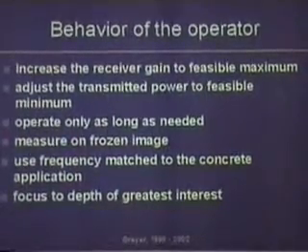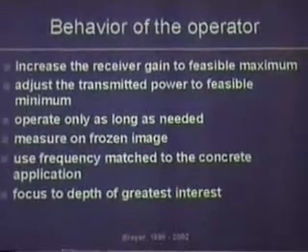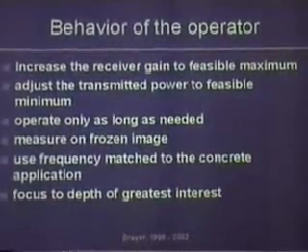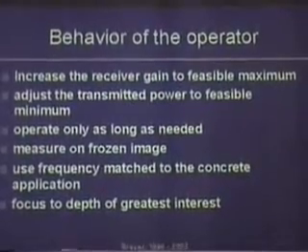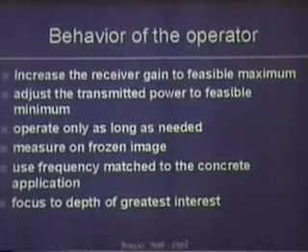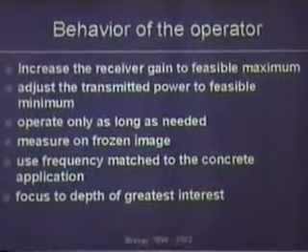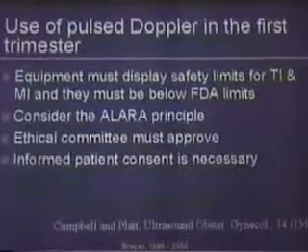Frequency and focal zone, everything must be adjusted properly. You should have it as it should be. Because if you adjust this properly, that means you use the frequency that is applicable in that particular case, then you will use less energy and you will be done with the examination faster than without it. Next, please.